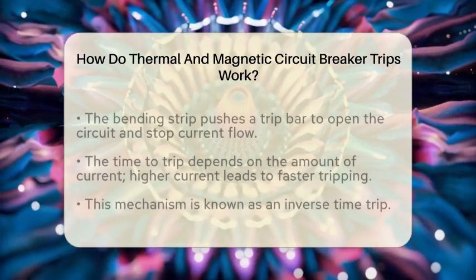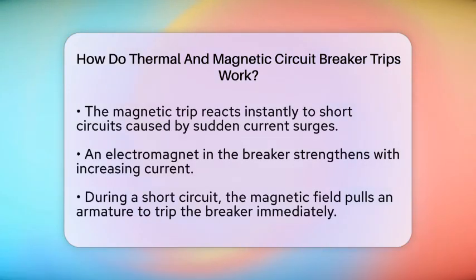When a short circuit occurs, the magnetic field quickly pulls an armature, which is a movable metal part. This action moves the trip bar to open the breaker immediately, preventing damage from the sudden spike in current.